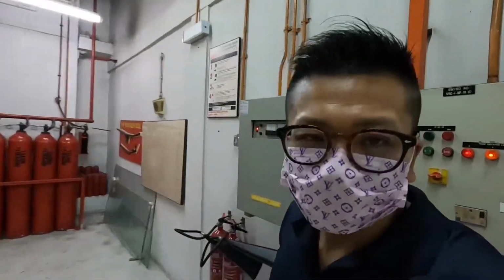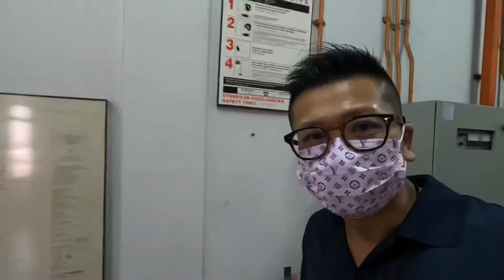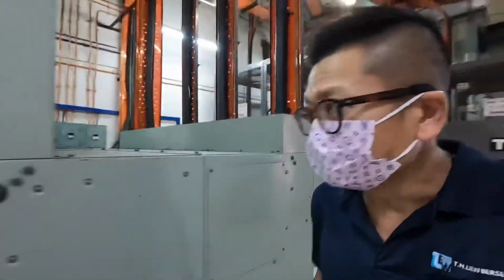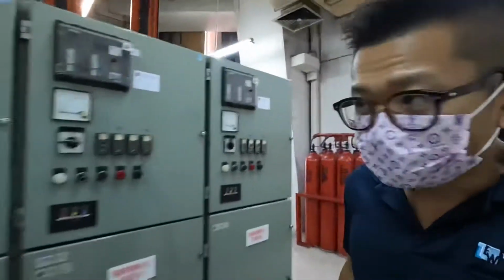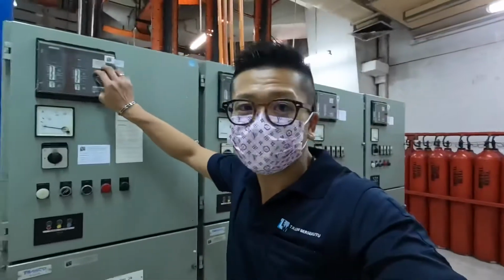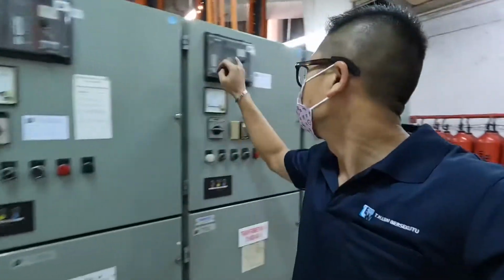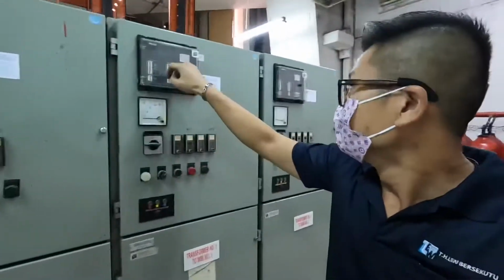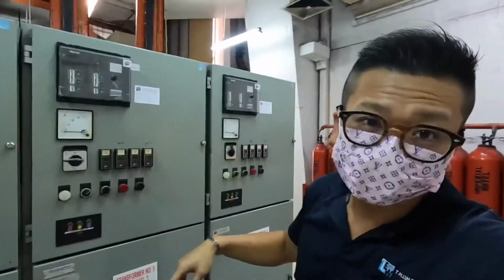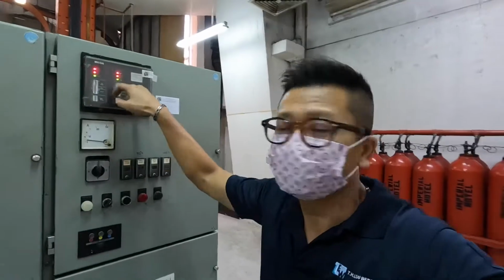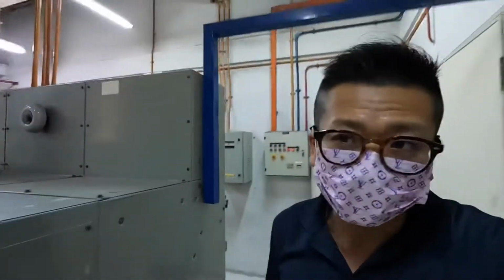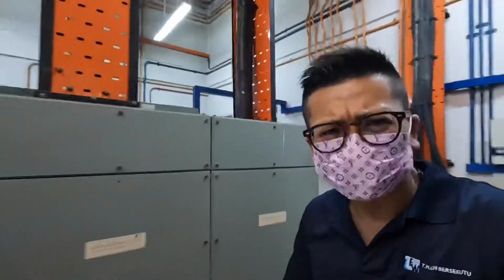Okay, here I'm inside the level 18 HV room. Here I just take a routine check on the HV room. This is the transformer and this is the VCB panel. Normally what I check is make sure the protection relay is in good condition. It depends on what protection relay the installation has, and then do make sure there's no unusual sound, humming sound from a transformer.